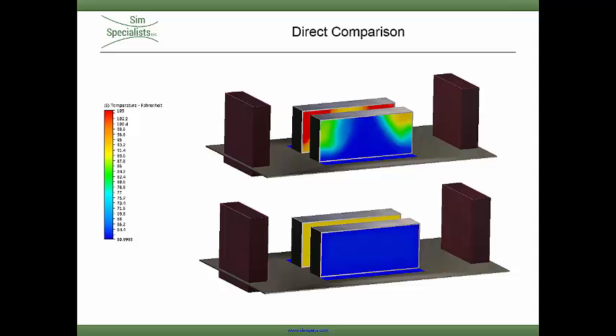Between these two designs, there is a 3 degrees Celsius difference in the average temperature exiting the servers, which equates to nearly 40 kilowatts that the CRAC unit must condition.